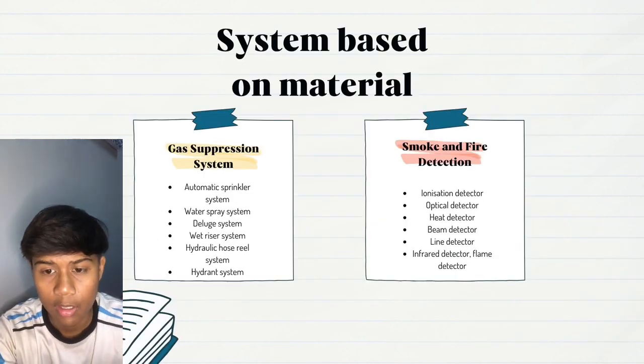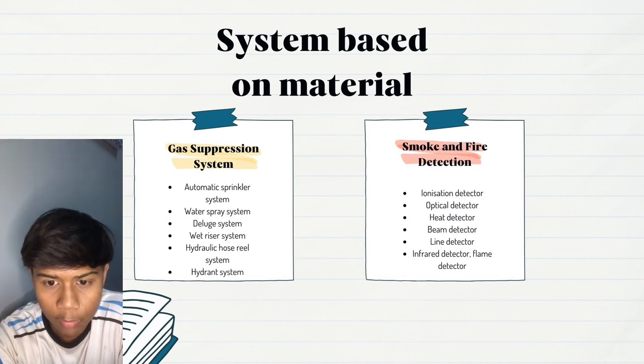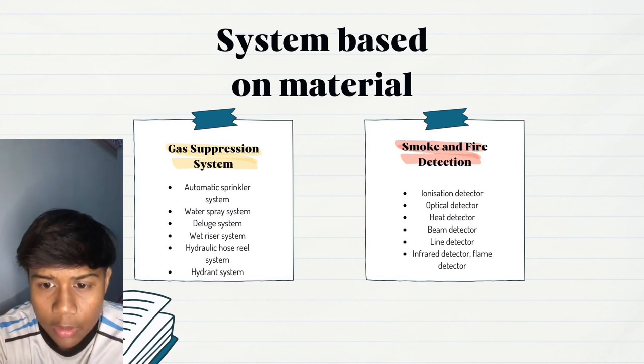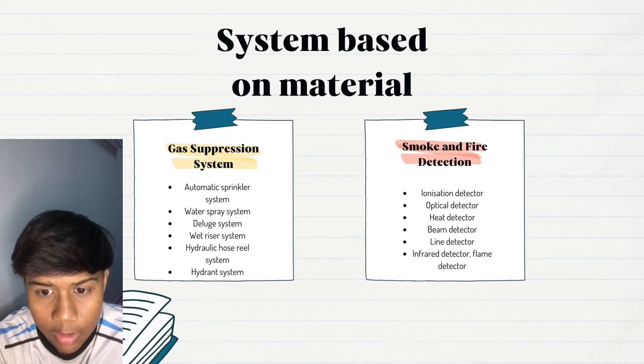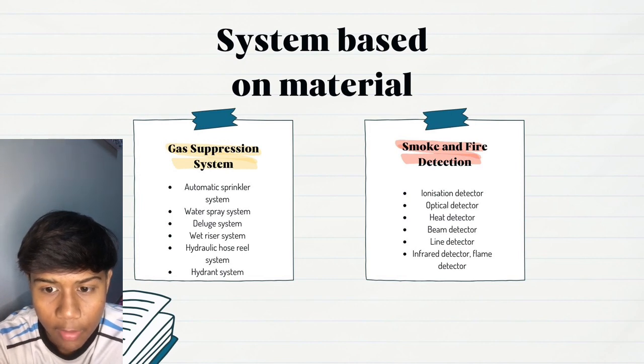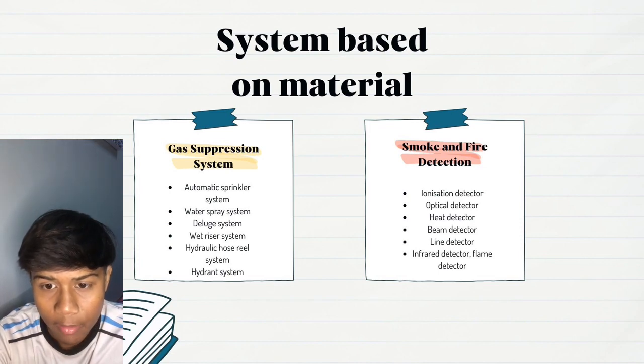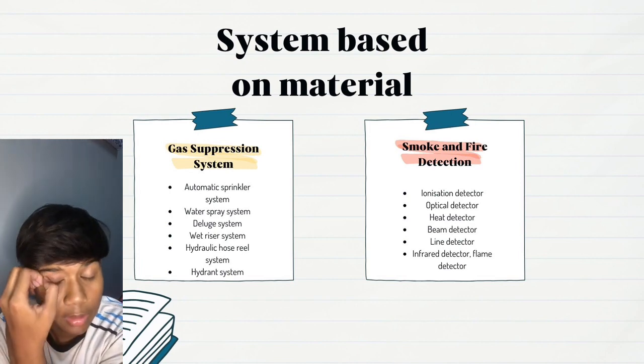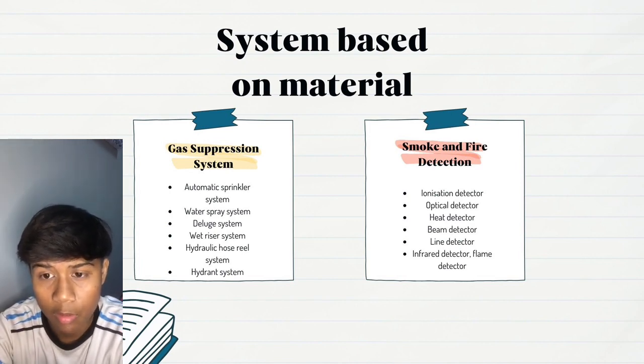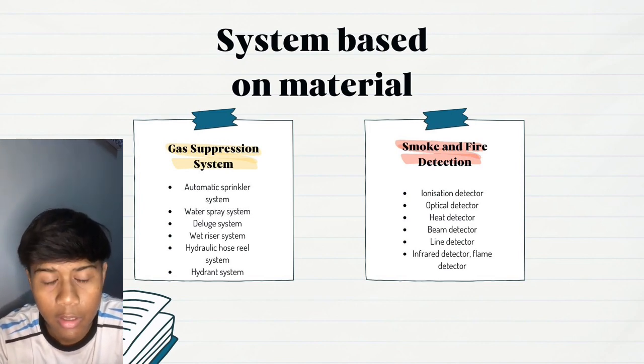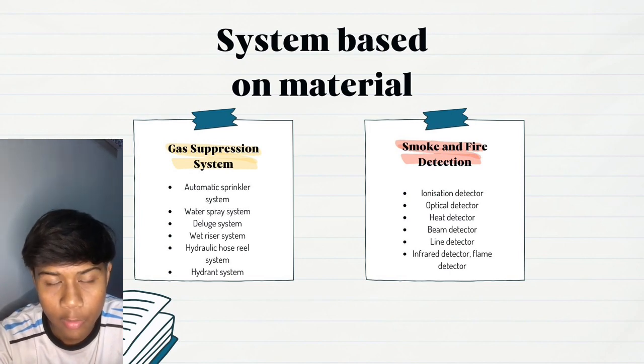Okay, systems based on material divide into two groups. First group is gas suppression systems, and second, smoke and fire detection. The gas suppression systems are the automatic sprinkler system, water spray system, deluge system, wet riser system, hydraulic hose reel system, and hydrant system. Next, smoke and fire detection: ionization detector, optical detector, heat detector, beam detector, line detector, infrared detector, flame detector. Most of them are detectors. Any building should install these, because before the building is constructed, they need to have permission from the firefighters for the safety of the building.